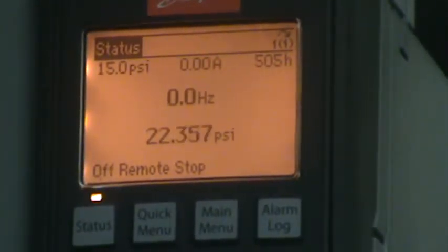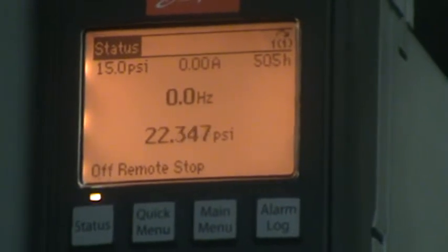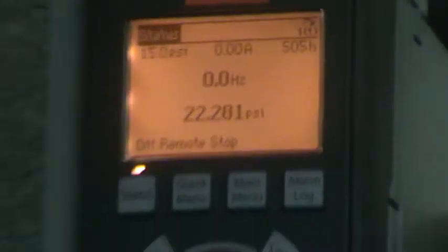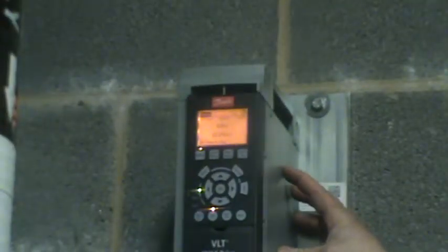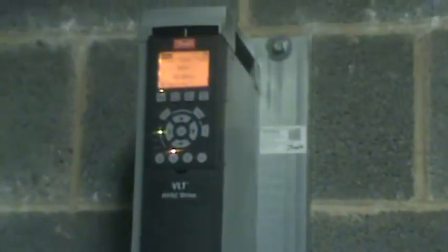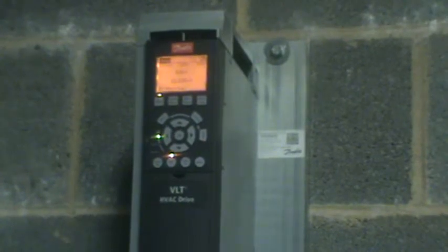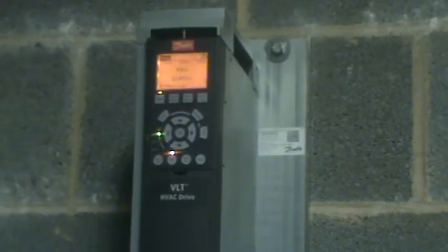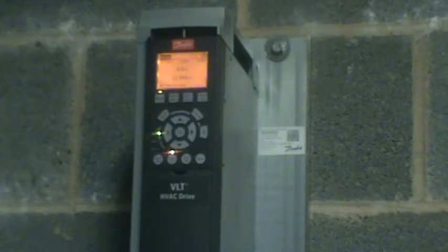When you turn these off, there's a capacitor bank in there that holds power. If you got to go in there and work, turn it off and go grab a cup of coffee. It can take a few minutes to discharge. Also, inside the back of this is a 600 volt DC bus. From here down, sure, work on it. From here up, call Danfoss. The 600 volts DC will knock you off that boiler and you won't know what hit you. So I normally tell guys don't screw with it.